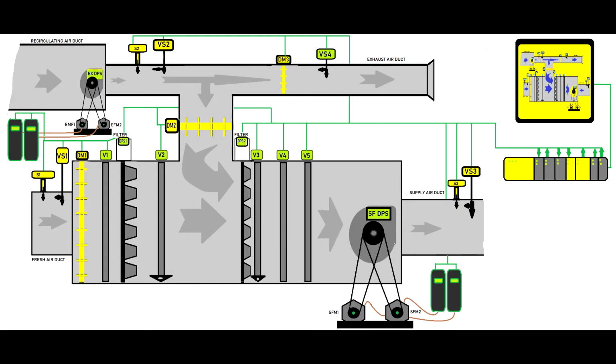So now the dampers slowly are turning on. Please don't forget, they are proportional. After the dampers are turned on, the fan motors will start to spin because they are controlled by a variable frequency driver. Then the air starts to circulate through the building. This is the order in which an air handling unit will start.